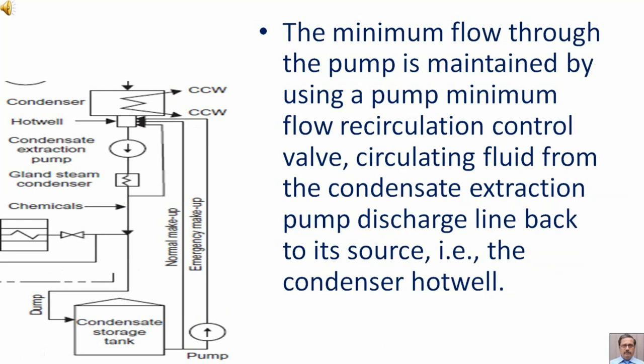This is the recirculation line and the recirculation control valve is located on this line. The minimum flow through the pump is maintained by using a pump minimum flow recirculation control valve, circulating fluid from the condensate extraction pump discharge line back to its source — that is, the condenser hot well.